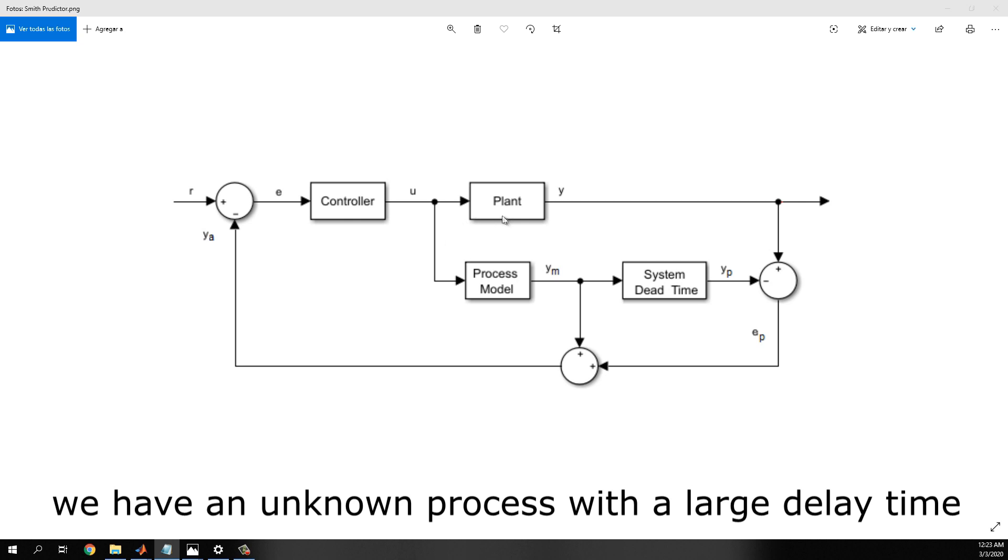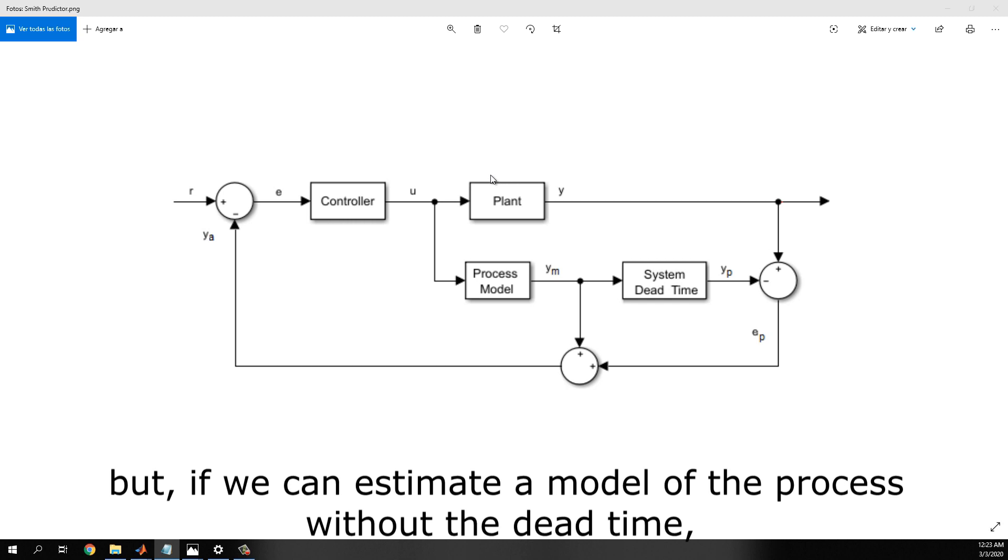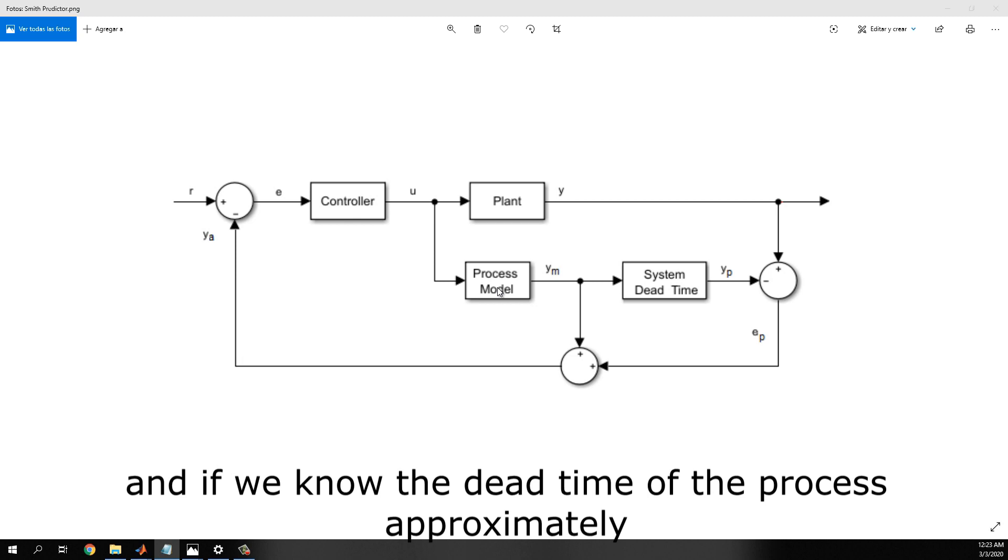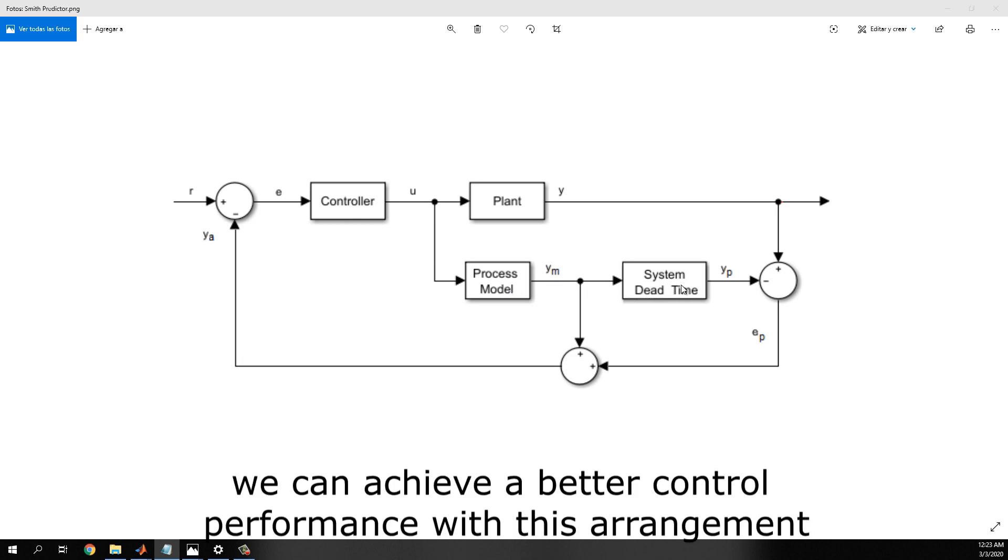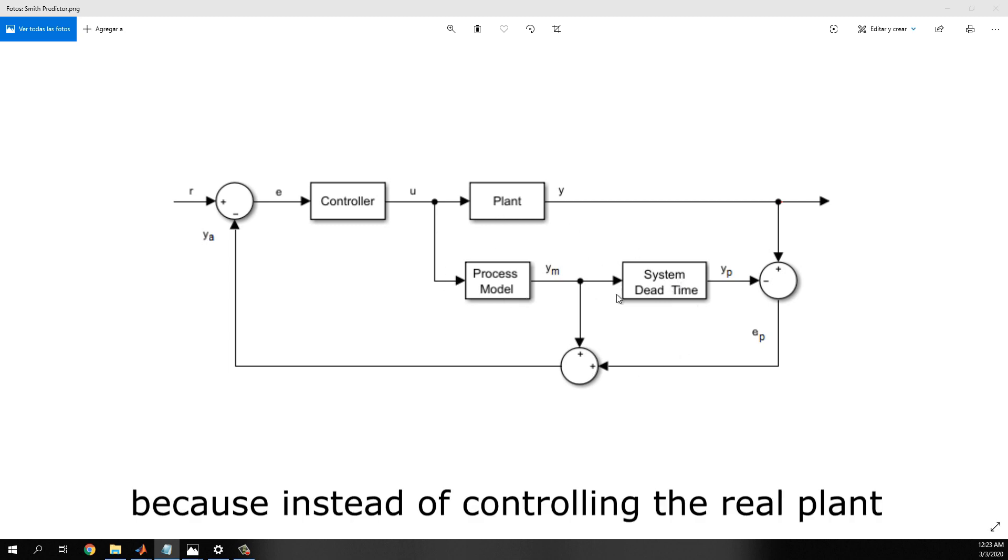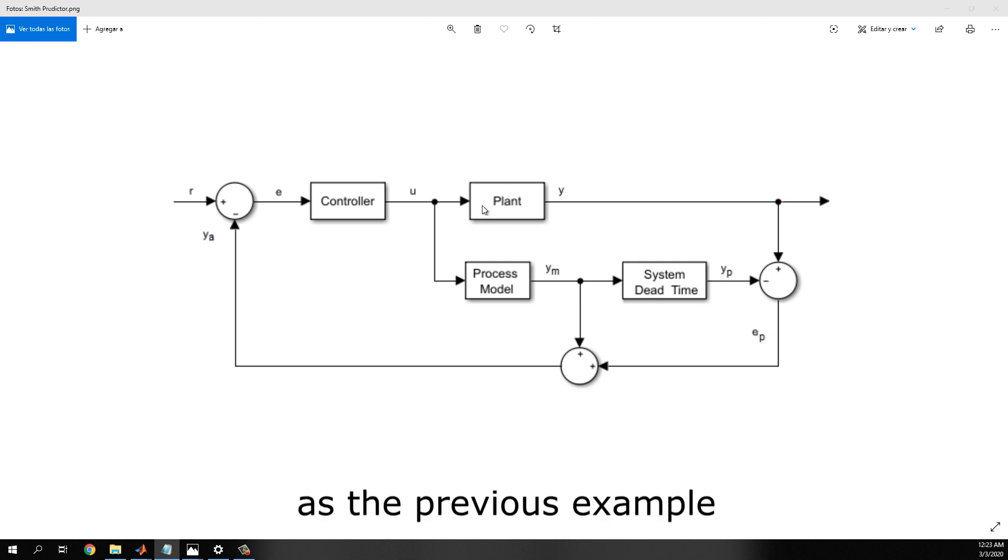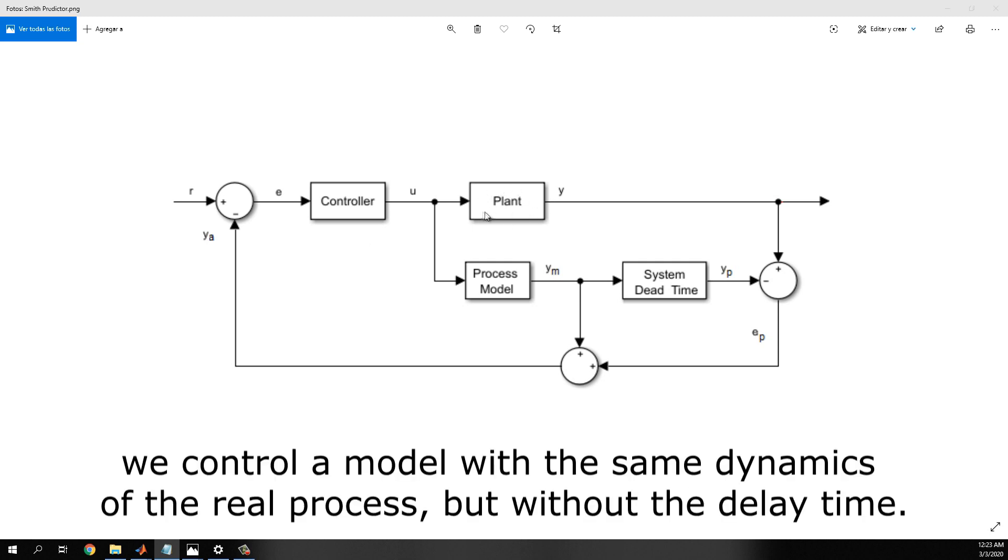So, we have a process with a large delay time, but if we can estimate a model of the process without the dead time, and if we know the dead time of the process approximately, we can achieve a better control performance with this arrangement. Because, instead of controlling the real plant, as the previous example, we control a model with the same dynamics of the real process, but without the dead time.